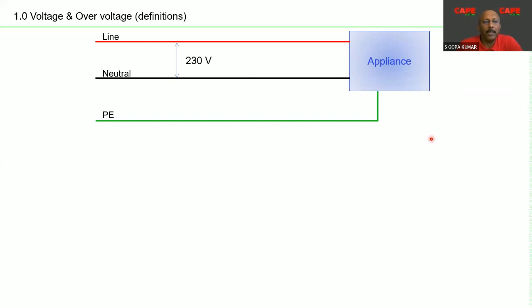First, we should understand, I'm just trying to explain the definitions of voltage, which is related to transient overvoltage protection. Because the protective devices, like all other protective devices, such as OCPD, RCDs, and other devices such as AFDD, these are operating in series. They disconnect the current, whereas SPDs are devices which are connected in parallel to the line. So this is very important to understand. So these are voltage operated devices.